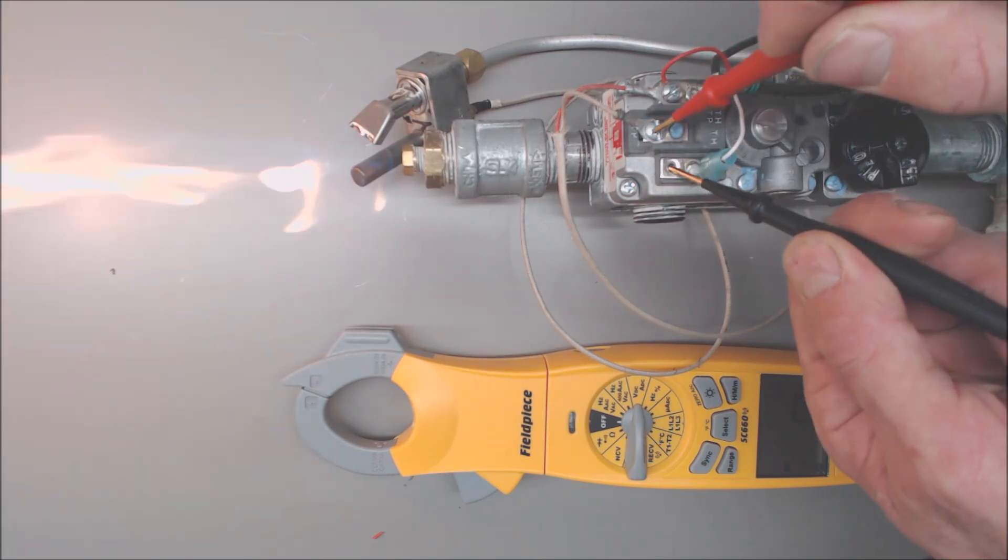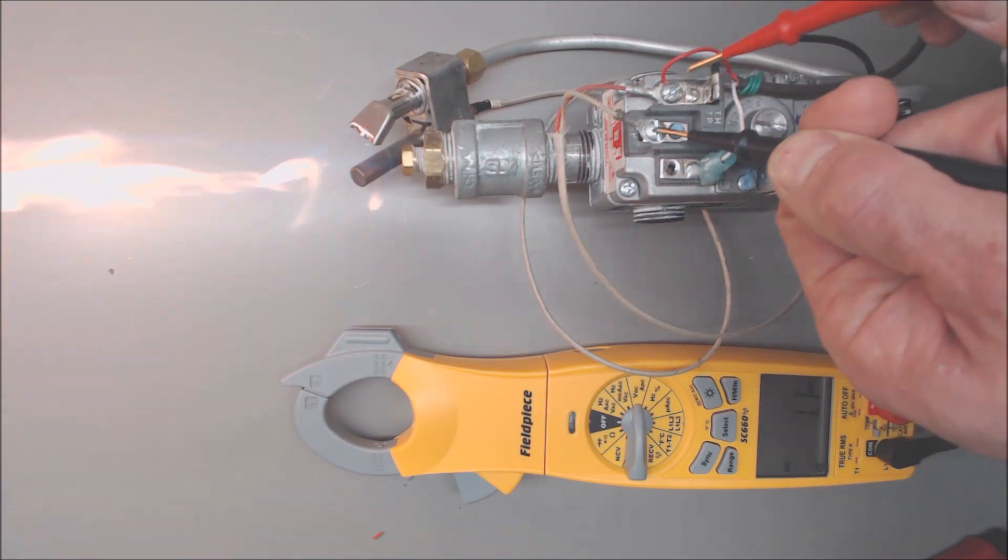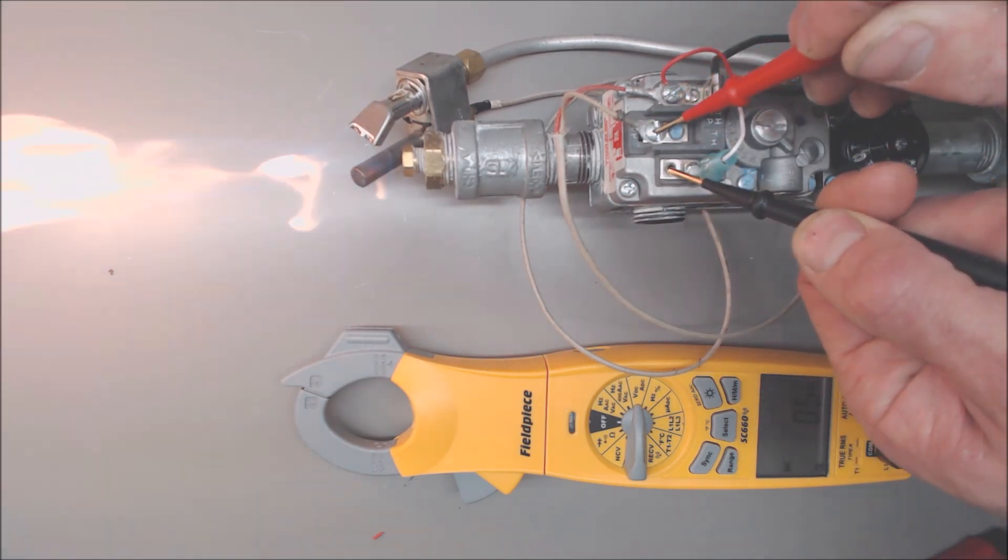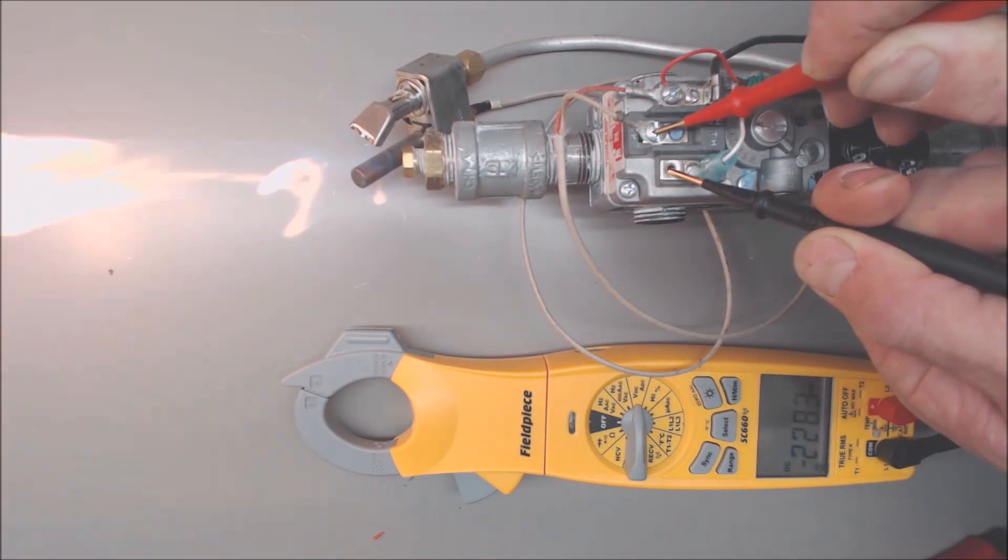If we check out over on this side, it'll be lower than whatever that is, so we're reading 222 millivolts. You can see that there's a significant voltage drop from where the pilot valve is wired into to where we have the main gas valve wired at. Presently we're reading 230 millivolts roughly, and you see that is actually enough to open up that gas valve.